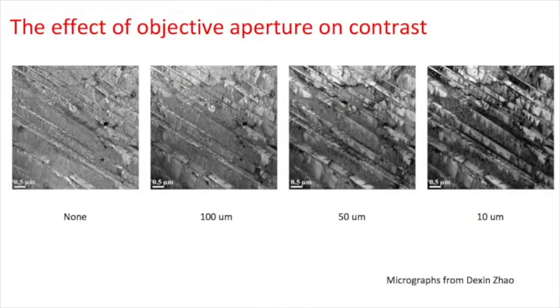All the images in this slide were taken from the same area of the specimen, with and without objective apertures. When no objective aperture was inserted, we get the best signal but the worst contrast. When we used the smallest objective aperture — in this case 10 microns — we get the best contrast but sacrifice some signal. To improve the signal-to-noise ratio when using a small objective aperture, you can either converge the beam or increase the image acquisition time. In this video, we showed you how to take good bright field TEM images. In the next video, we'll show you how to acquire the diffraction patterns on the camera.